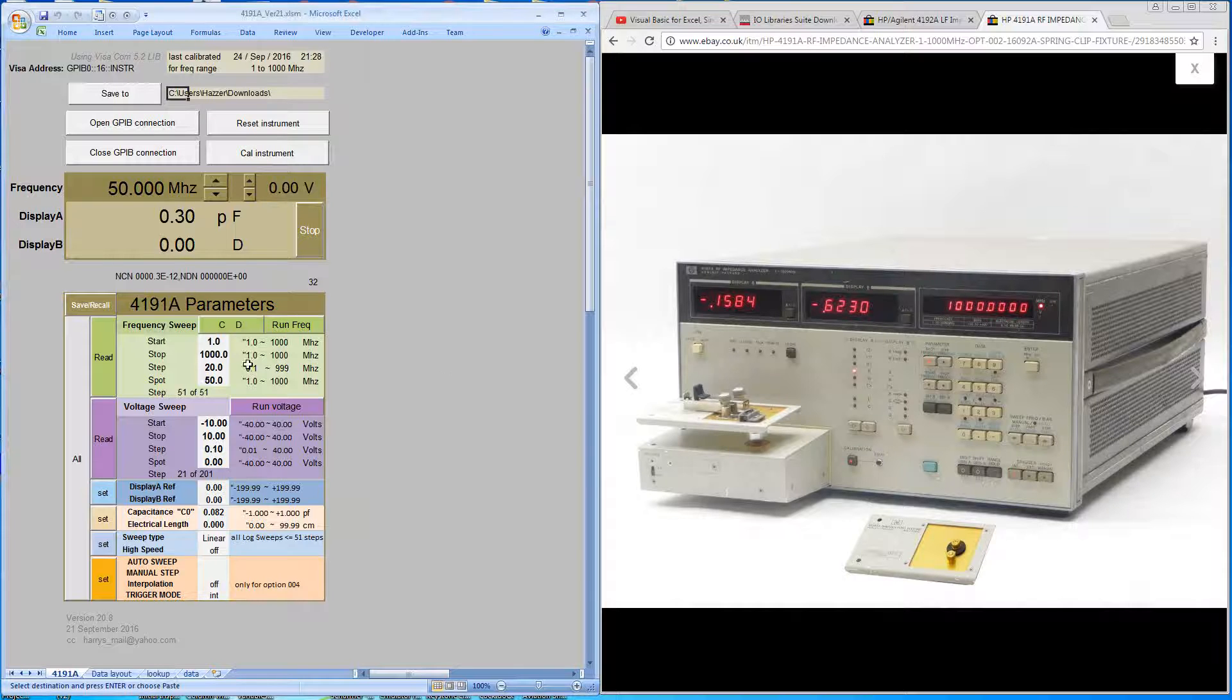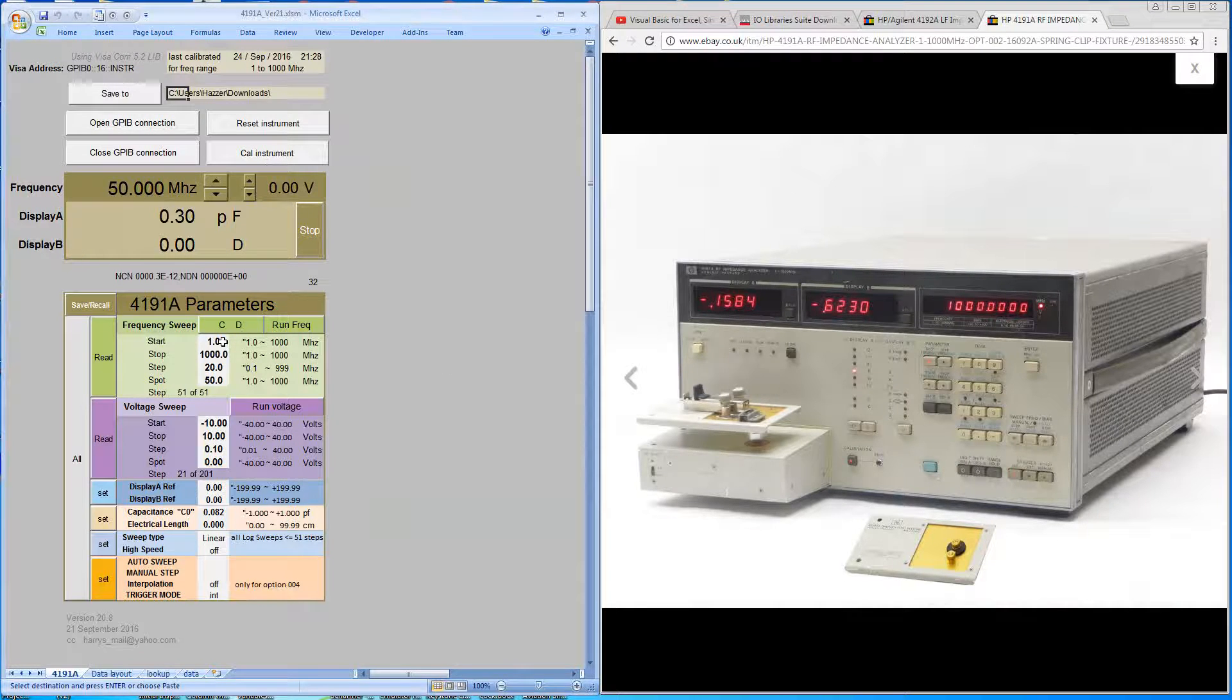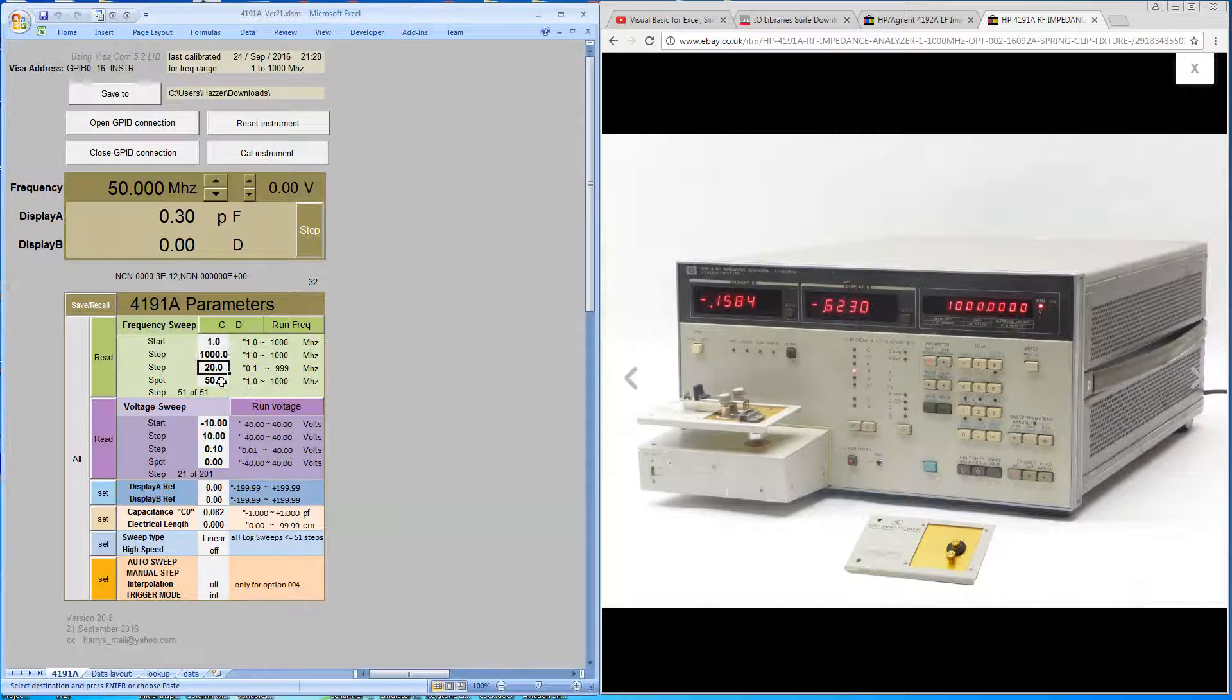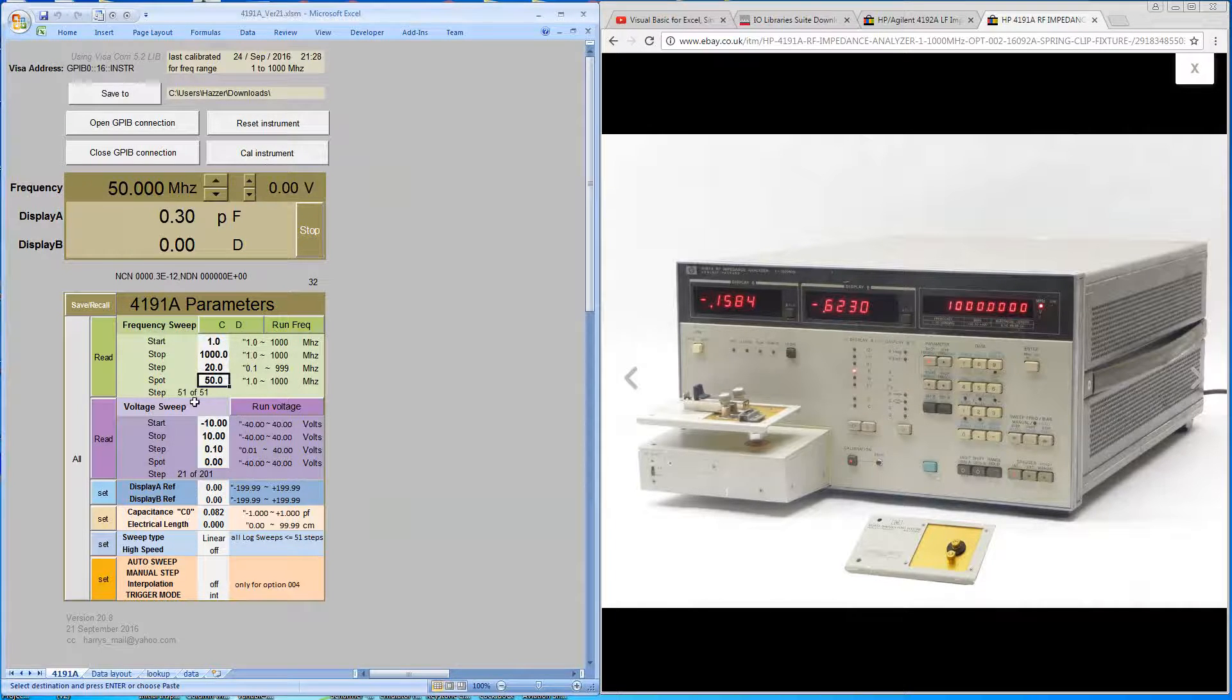Just walking through the interface, the user can enter the start and stop frequencies, the step frequencies and the spot frequency. The machine will calculate the number of measurements that were made over that frequency range.